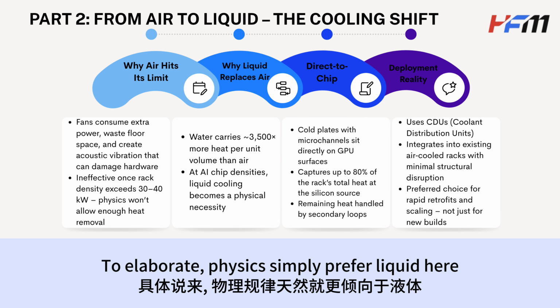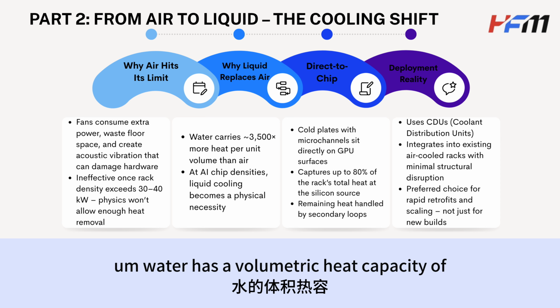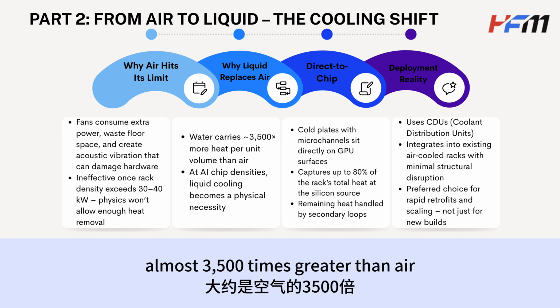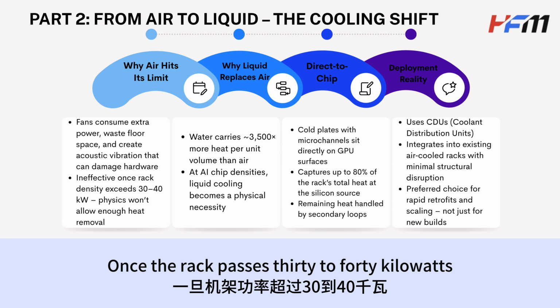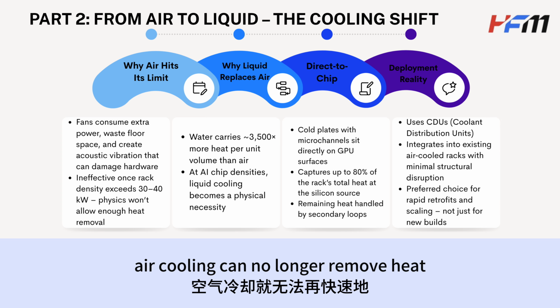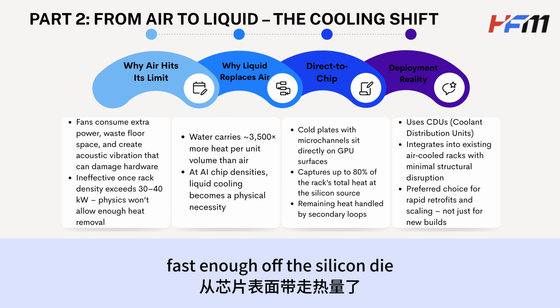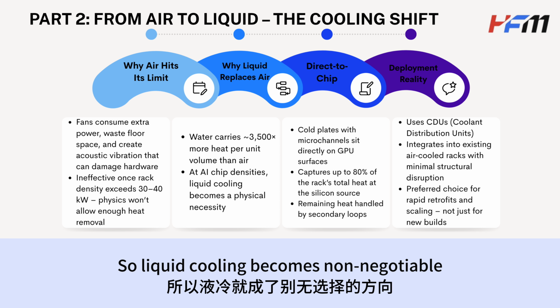To elaborate, physics simply prefers liquid here. Water has a volumetric heat capacity almost 3,500 times greater than air. Once the rack passes 30 to 40 kilowatts, air cooling can no longer remove heat fast enough off the silicon die. So liquid cooling becomes non-negotiable.